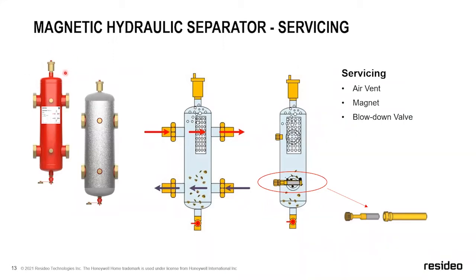There are a lot of determining factors as to what the expected lifespan is. If it's a water only system, you're probably going to see 15 to 25 years out of it. If this is a glycol system, you will see that air vent fail on a much more regular basis. And those of you that have been in the industry for a long time, I'm sure you've seen that. Air vents just don't last in glycol systems. And I'm going to shed some light as to why that is. I'm not a big fan of using glycol unless you absolutely have to. There's a lot of reasons for that.